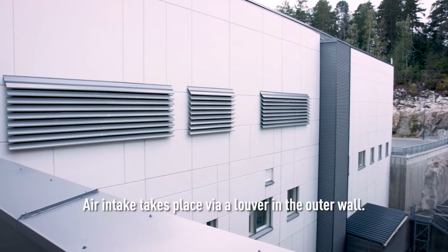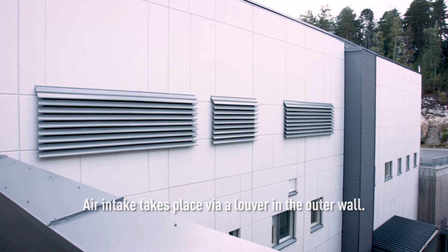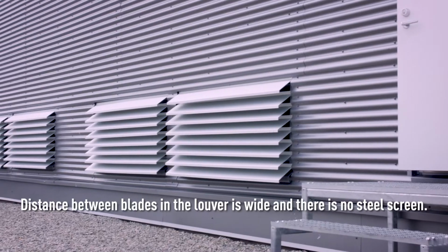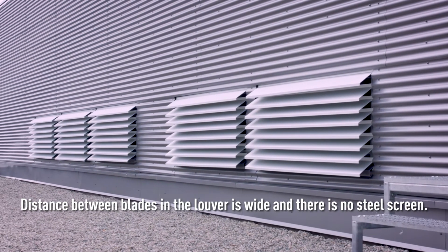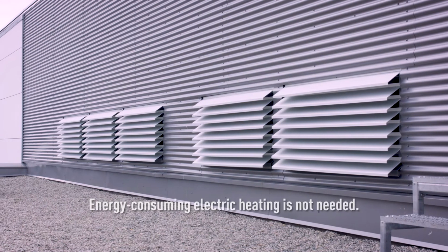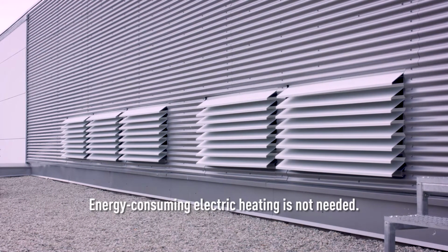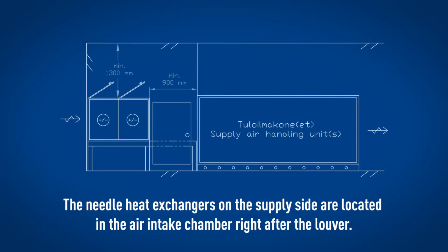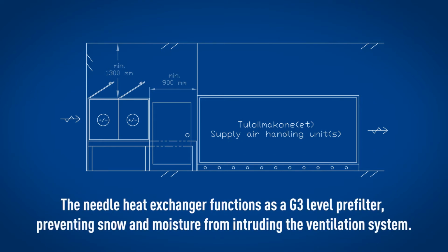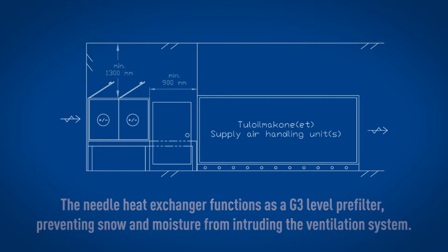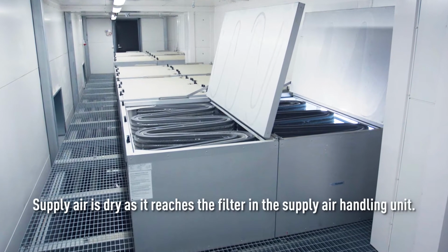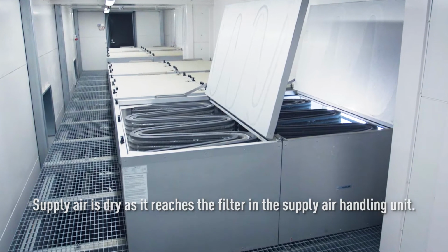Air intake takes place via a louver in the outer wall. Distance between blades in the louver is wide and there is no steel screen. Energy-consuming electric heating is not needed. The needle heat exchangers on the supply side are located in the air intake chamber right after the louver. The needle heat exchanger functions as a G3 level pre-filter, preventing snow and moisture from intruding the ventilation system. Supply air is dry as it reaches the filter in the supply air handling unit.